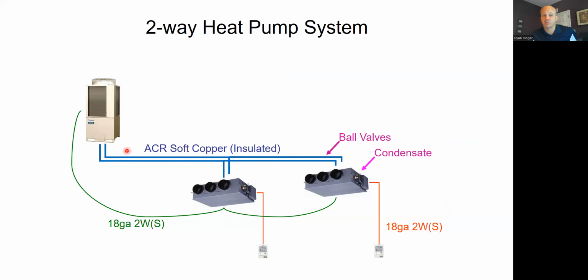So the size of pipe you need will be pretty large if you have a 20, 30, 40 ton unit versus a 6-ton unit. But the piping starts out large and then it just keeps tapping off, kind of like ductwork does. You start off with a big, huge duct, and as you get further down, you pull some zone duct off, and now your remaining duct gets smaller and smaller as you get further down the line. You'll insulate both of these lines because the metering devices are out in the unit, like we said before. You may or may not have thermostats on the wall. Some of the times they'll have the handheld remote control. Other times they'll have thermostats on the wall.